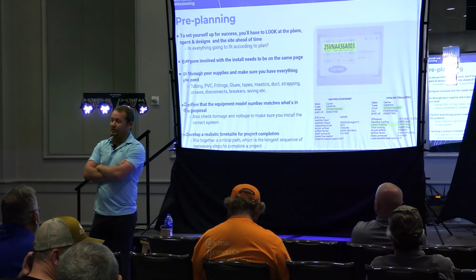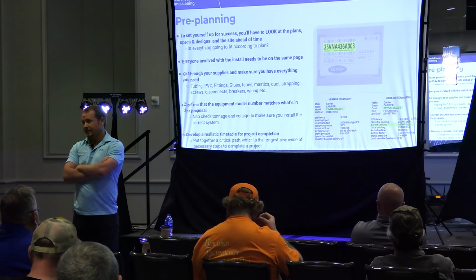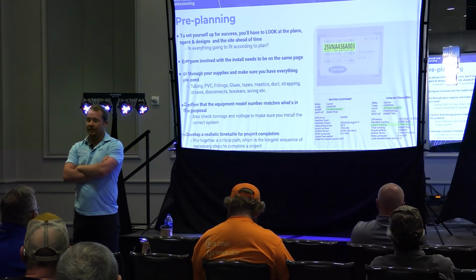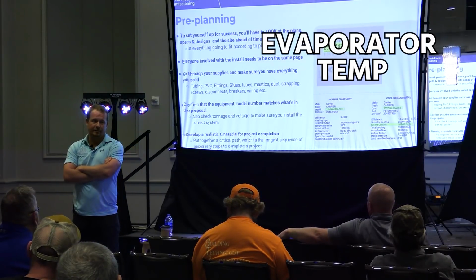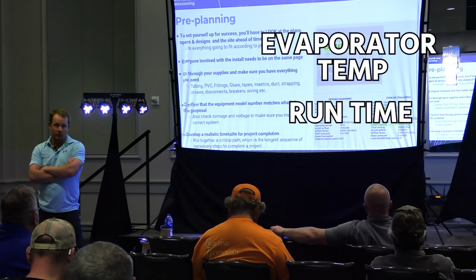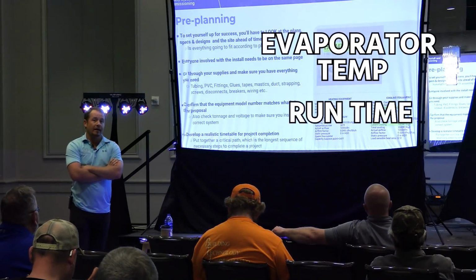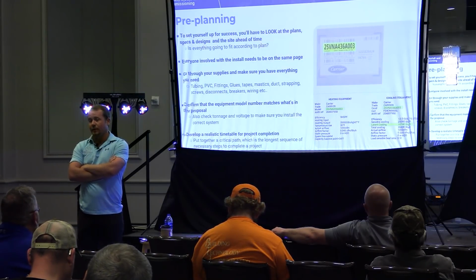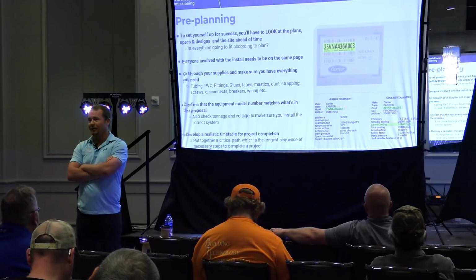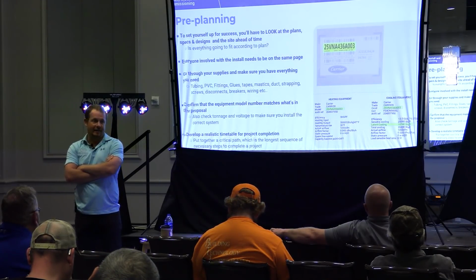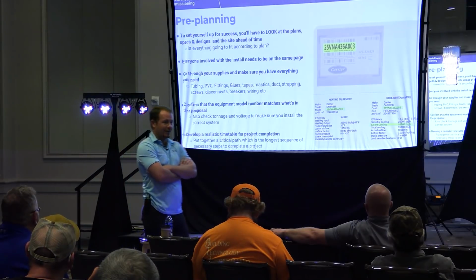So dehumidification, real simple — it's huge in this market. Dehumidification is a function of evaporator temperature and runtime, full stop. If you want to pull more moisture out with the equipment, run the system more with a lower evaporator temperature. The easiest way to do that is to put more load in. So if you have a house with a real humidity problem, pull all the insulation out of the attic — it'll take care of the humidity problem.